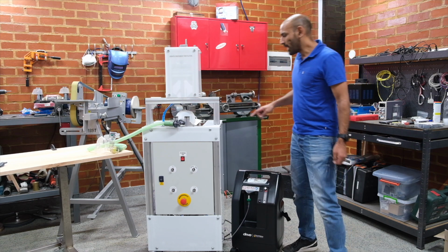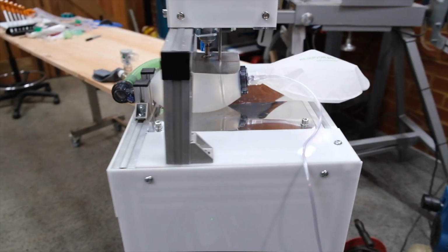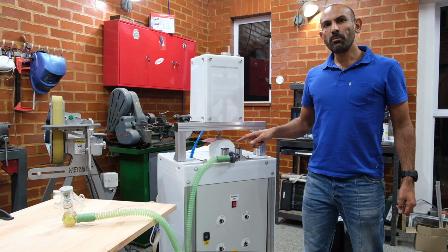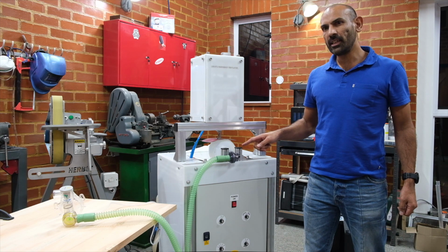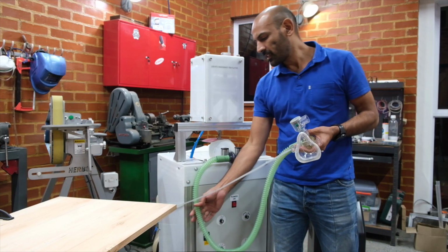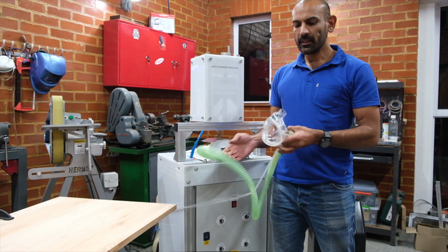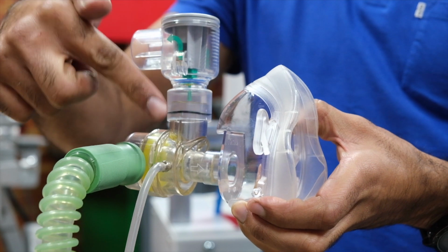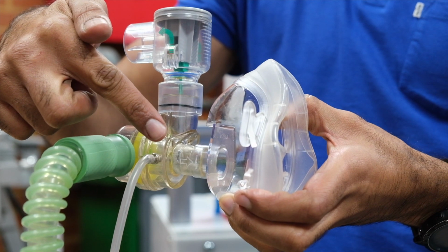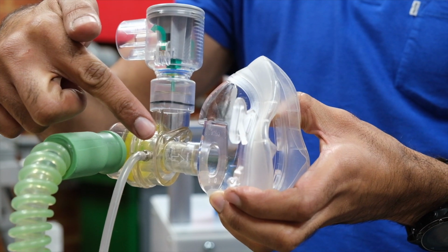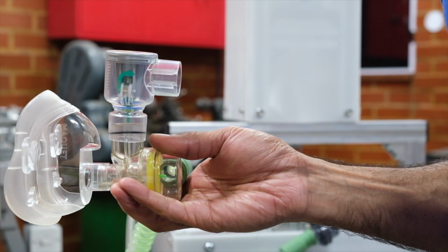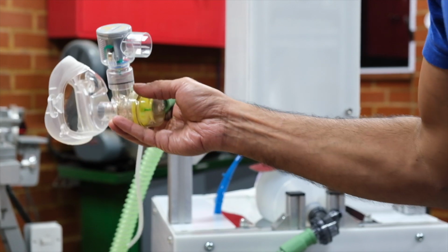If you look around the back of the machine, you'll see how the air connection from the valve connects to the Ambu bag. The machine uses a standard Ambu bag, or BVM, fitted with a safety relief valve. It's then connected to the CPAP mask using a normal corrugated airway. The CPAP mask is fitted with a PEEP valve, and it's also connected on the exhalation side to this airline. This airline is then connected to the pressure sensor, which provides the trigger for the assisted ventilation mode.